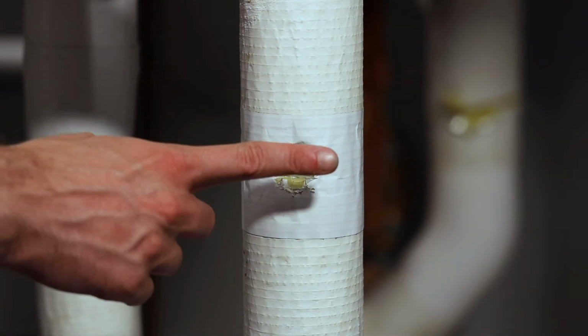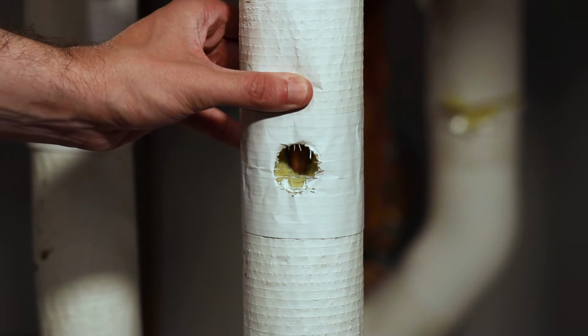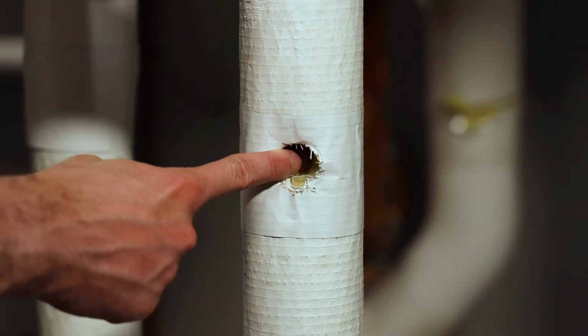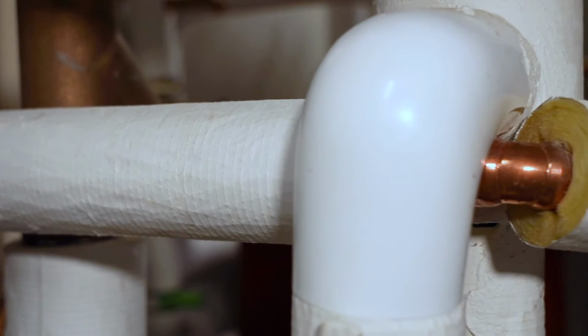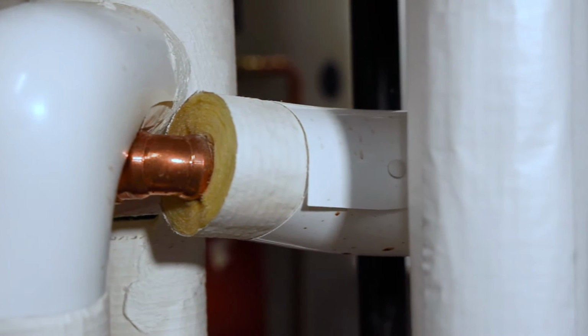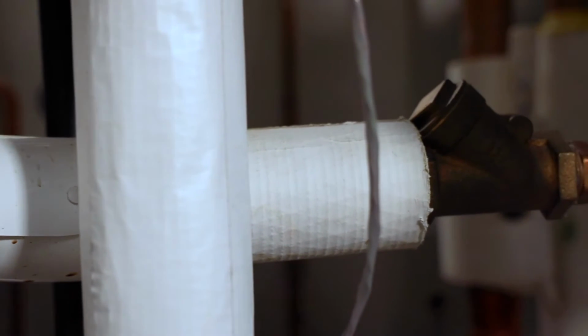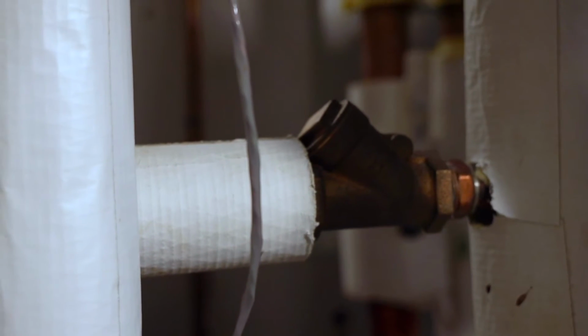Evolution sensors are unique in that they sense the temperature inside of the pipe through an external sensor. It's not measuring the temperature of the piping material, it's actually reporting the internal water temperature based on the piping size and material. For this reason, it's important to make note of the material and size of the piping when installing the sensors. And we'll use that information a little later when we set up the app.